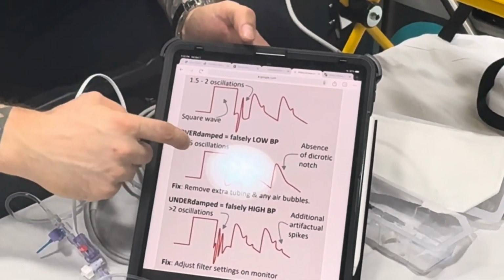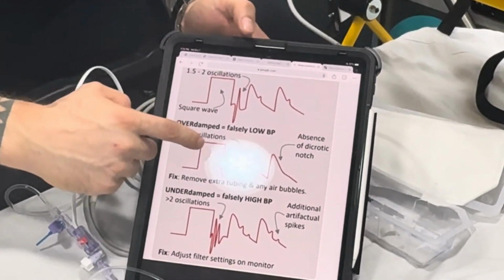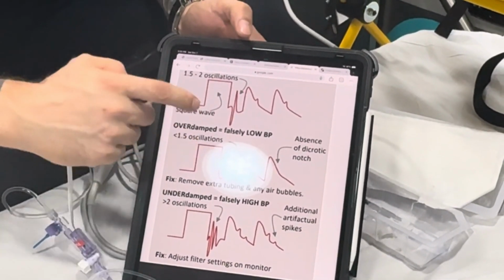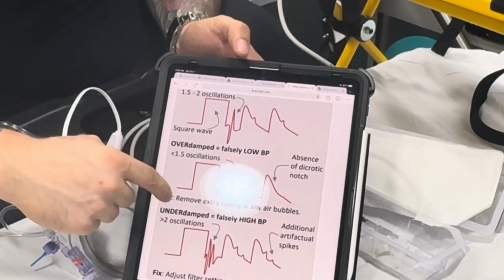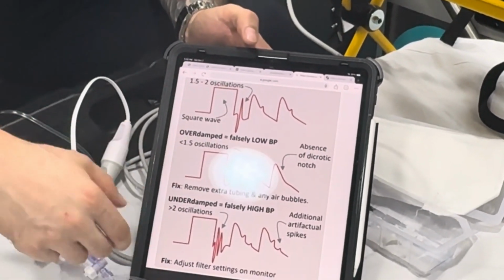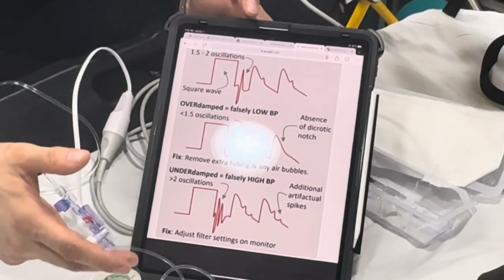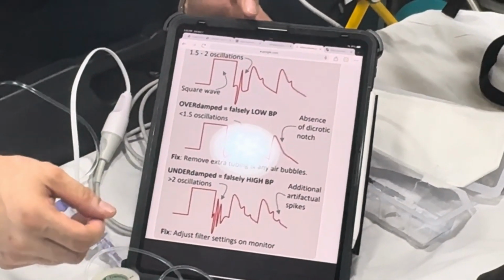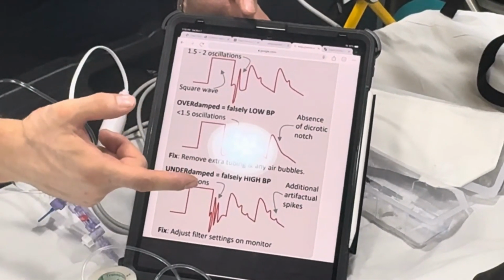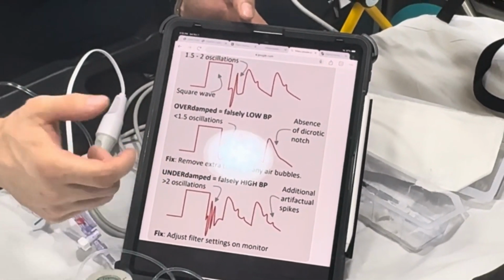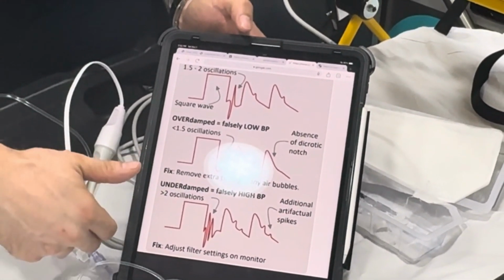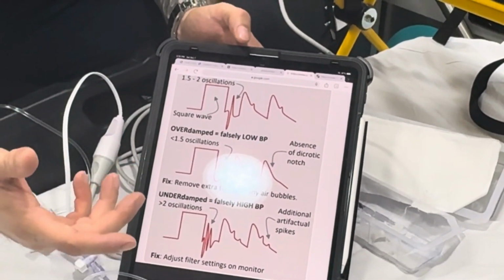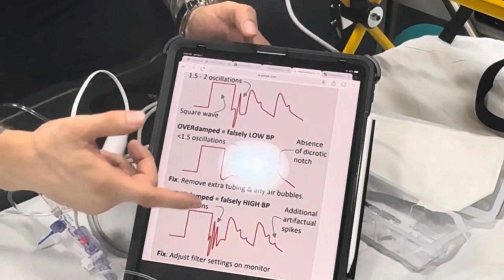So they call this over-damped, and over-damped means your blood pressure is falsely low. Usually they'll tell you to remove the extra tubing. Sometimes you may have excess tubing, or somebody added more tubing than necessary, or you may have air bubbles in the line. So what you're going to do is look at your transducer, look at all the tubing, take out excess tubing, and reflush the system so you have no air bubbles.